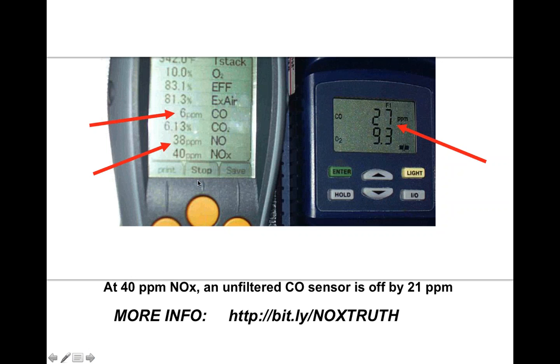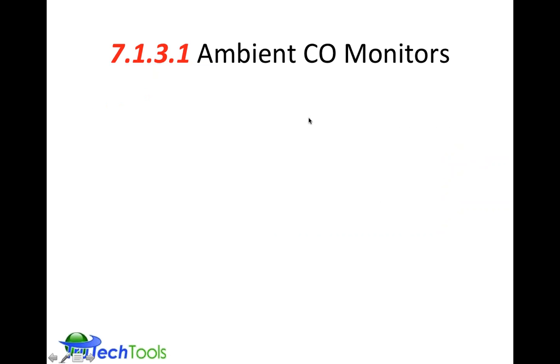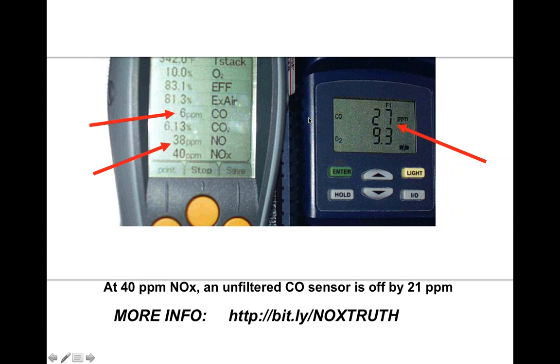But if you do the calculation, the NOx gives about 50% of its reading to the CO sensor. So about 50% of 40 or so is 20. If you add 20 to 6, you get in the range of 26, 27. So this is why this meter reads high. It's not because this one is broken or defective in any way. This one is reading CO plus NOx. The other meter is reading CO exclusively.